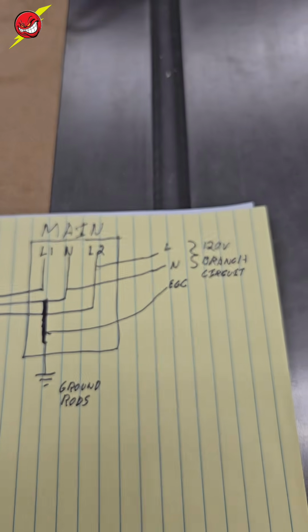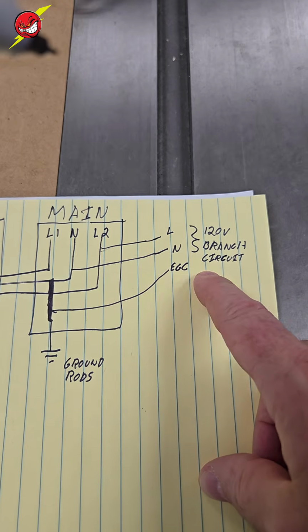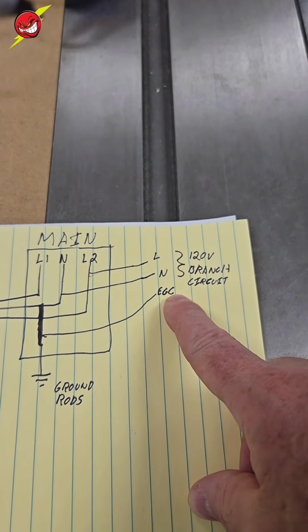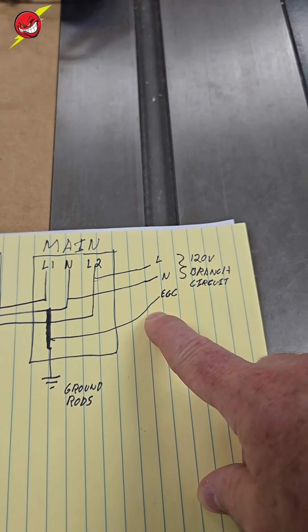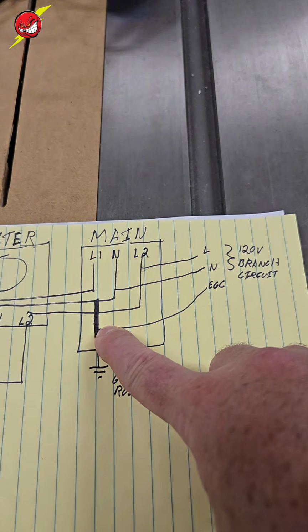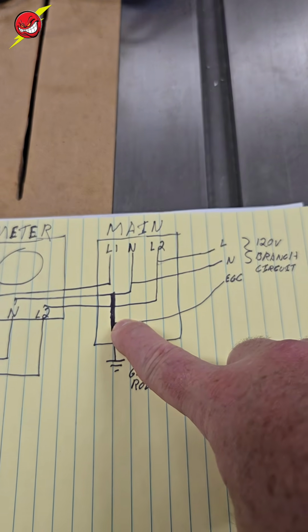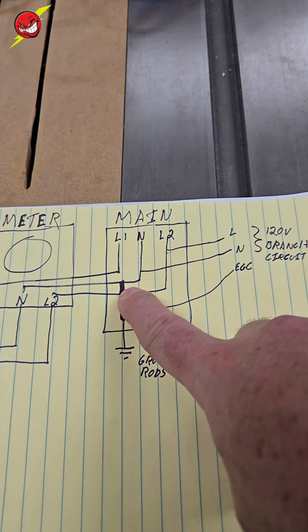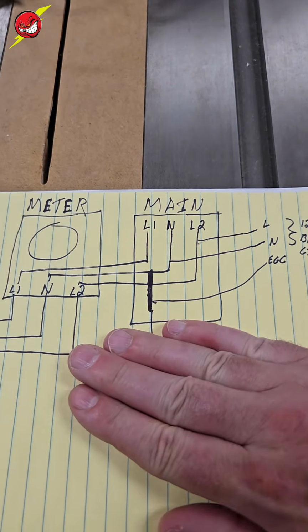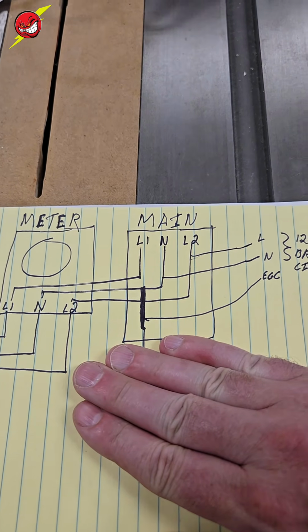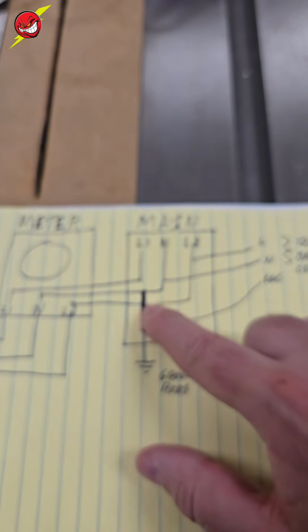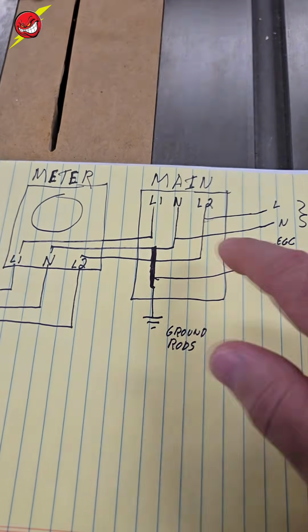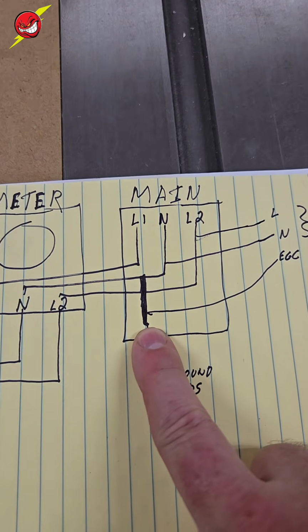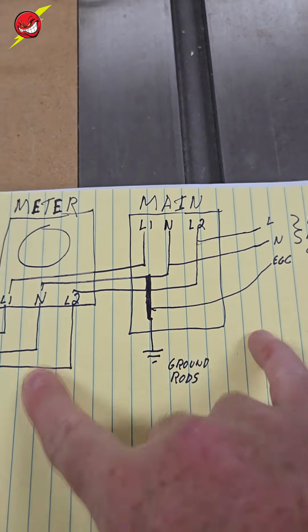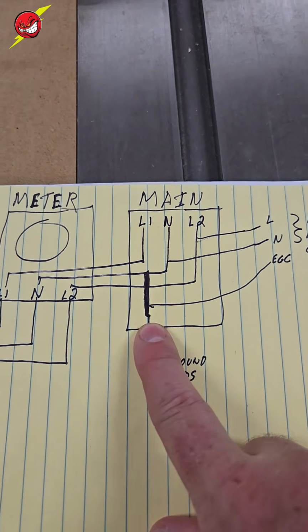Uh-oh, for whatever reason, we have a fault and our line goes to our equipment ground. That fault is gonna go through our intentionally constructed low impedance path, which is the equipment grounding conductor, all the way back to our main panel, which is bonded to the neutral. Again, we're ignoring our earth connection. We don't need to have that at all for this to go all the way back to the source and trip that circuit breaker. Connecting to the earth has nothing to do with this effective ground fault current path, and it will not trip a circuit breaker.